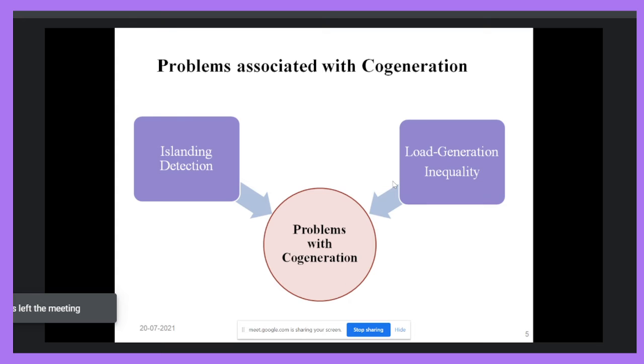Managing generation is limited. Suppose there is one generator, we cannot generate electrical power more than its rating. More than the generator rating, we cannot generate power. So if a larger load is connected to the system, we have to disconnect the load. For that we require a load shedding technique.